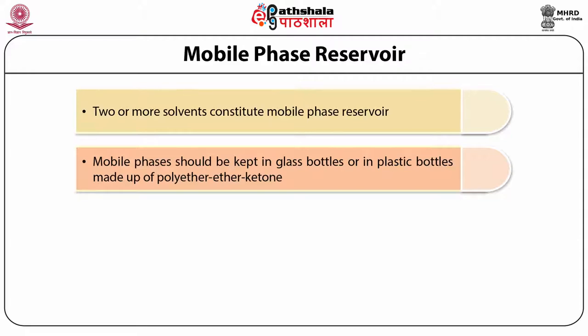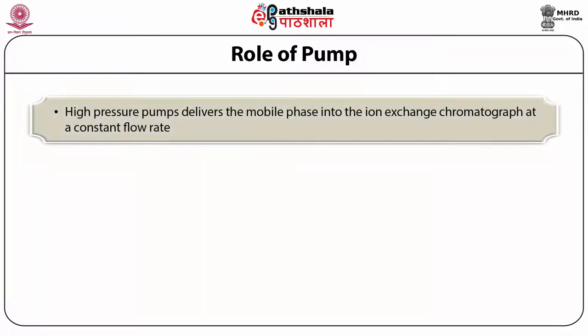For degassing, the solvents are vacuum treated for approximately five minutes followed by helium purging. Then, these solvents are kept under helium atmosphere. After discussing about the mobile phase reservoir, let me tell you about the role of the high pressure pump used in Ion Exchange Chromatography. The high pressure pump delivers the mobile phase into the Ion Exchange chromatograph at a constant flow rate.